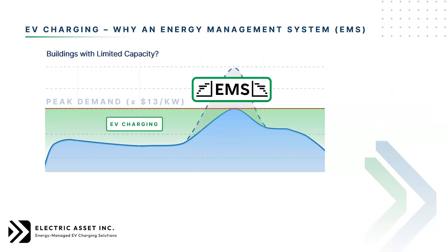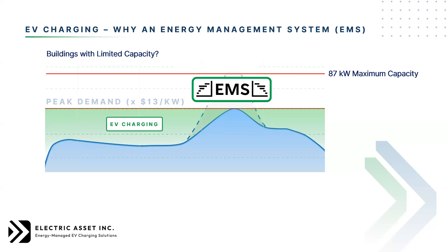The other impact and reality of an EMS is also to manage a building's limited capacity. So again, this peak demand management is basically a way to financially make EV charging cheaper and not pay peak demand fees. But there's also the ability to manage the capacity of a building. Under this scenario, let's say this building needed 100 kilowatts to give everybody full power, but it only had 87 available on its system. So instead of 100, we basically set the EMS to 87 kilowatts.